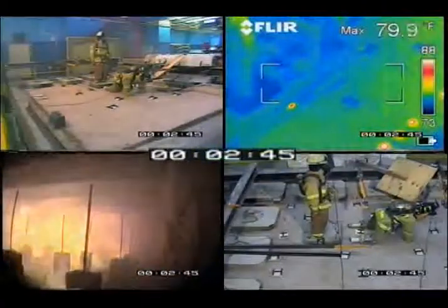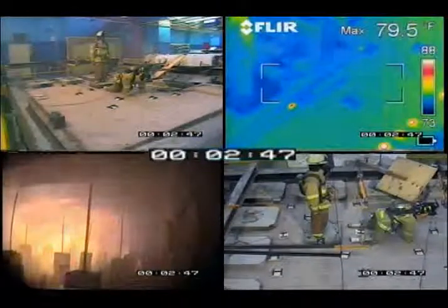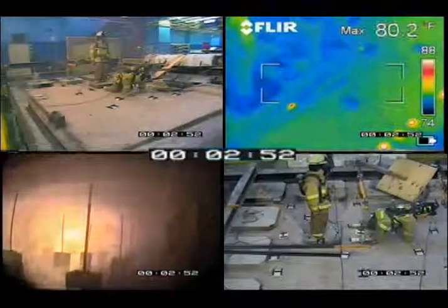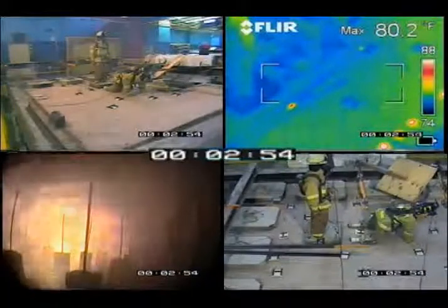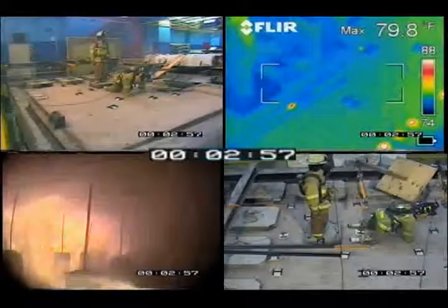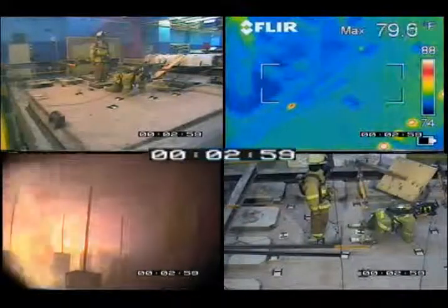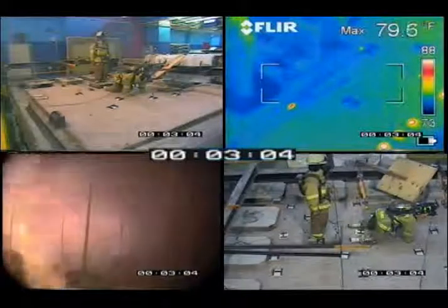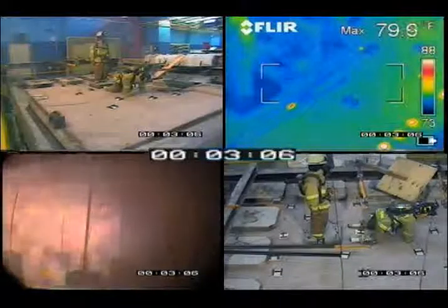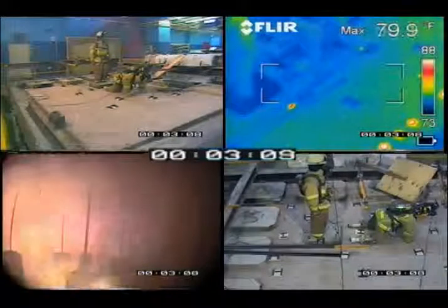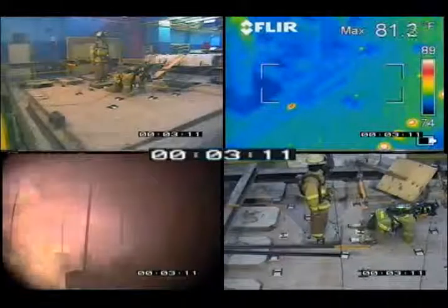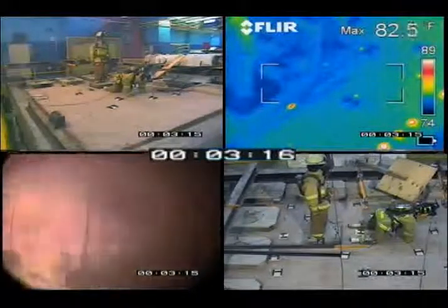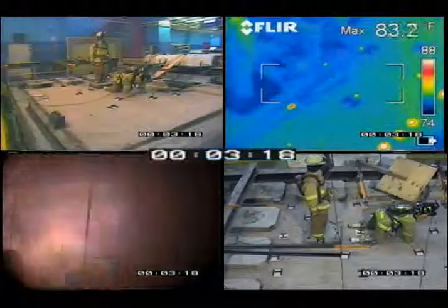The highest recorded floor surface temperature is 75 degrees, while the highest recorded temperature on the assembly structural elements is 1341 degrees. The measured maximum deflection of the floor is approximately 1/4 of an inch. At 3 minutes, the entire floor structure is fully involved and free burning. An interaction of both the turbulent behavior of the fire and the ignition of pockets of richly proportioned combustible gases creates the fire behavior displayed from this point until the end of the test.